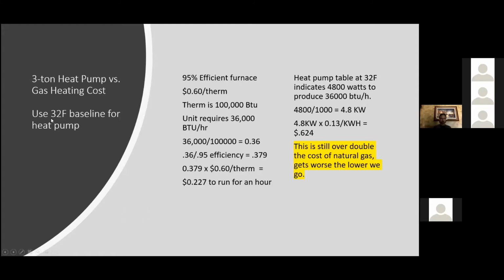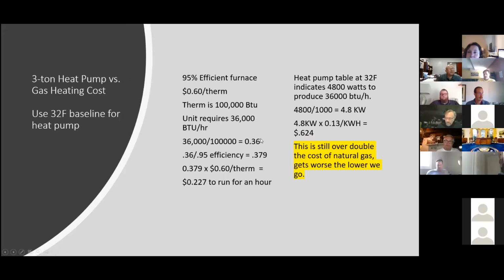And for a heat pump, we have to know the temperature to get the rating for it. So back to the gas, because we're not going to be using gas at the heat pump. This is the comparison. We have to produce 36,000 BTUs per hour. So 0.36 therm, corrected for its efficiency, 0.379, costs 23 cents an hour to produce that amount of heat. Conversely, the heat pump, and I'll show you the table here in a second, 4,800 watts. Now, if you think 4,800 watts, it's a pretty big electric wall heater, for example. 4.8 kW at 13 cents a kilowatt hour residential rate costs 62 cents versus 23 cents.